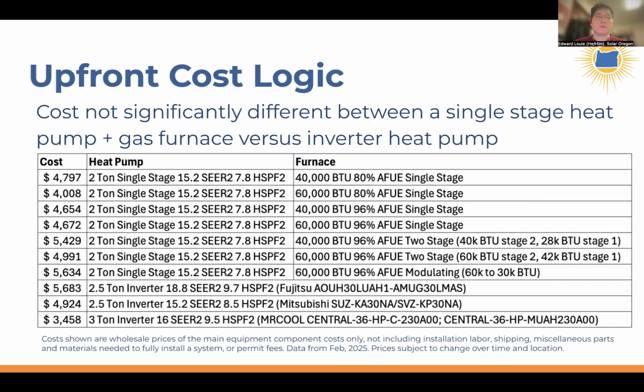Now, upfront cost, there's actually not a significant difference in price between a system that has a heat pump with a furnace, and we're talking about typically a system with a relatively cheap and simplistic heat pump and then a relatively cheap and simplistic furnace. So, the cost of two cheap components together equals roughly the cost of one very advanced cold climate heat pump that has the inverter so that it can modulate to very low levels of heat output on a mild day. But then that inverter can really speed up the speed of the compressor so that you can maintain heating output on a very cold day.